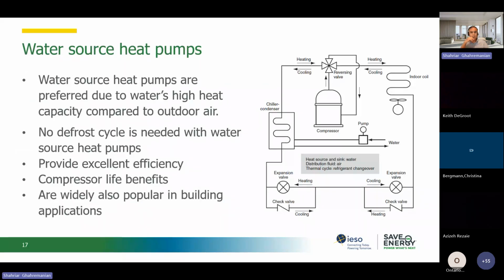As I talked about the different types of heat pumps that exist, one of them is water source heat pumps. Water source heat pumps actually are preferred, and they are better because water has higher heating capacity compared to air. Water can store energy 4 times more than air in itself. So that is why we can transfer a larger amount of heat through this equipment that we want to install.